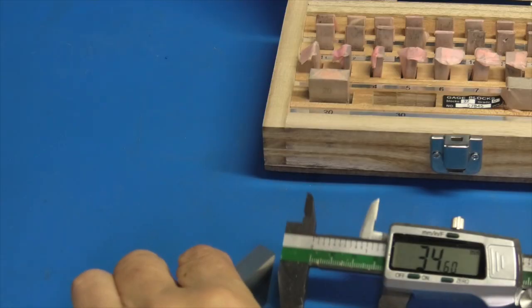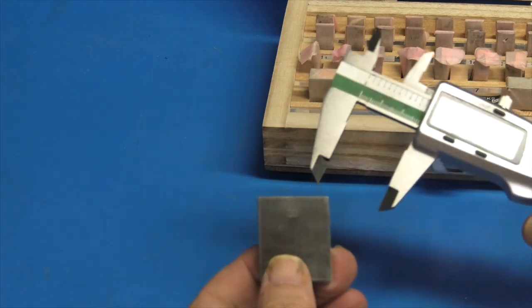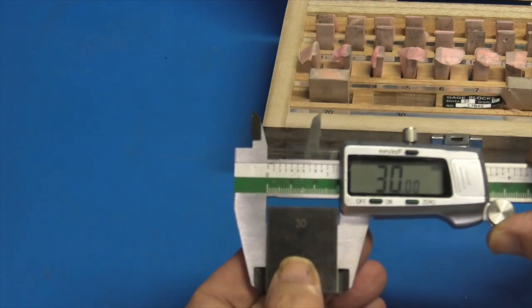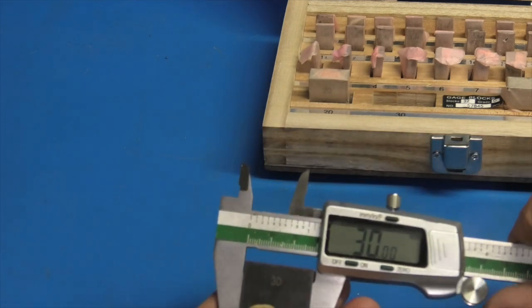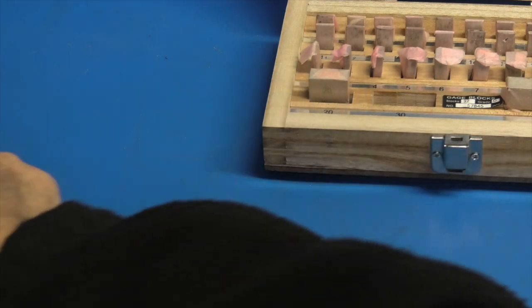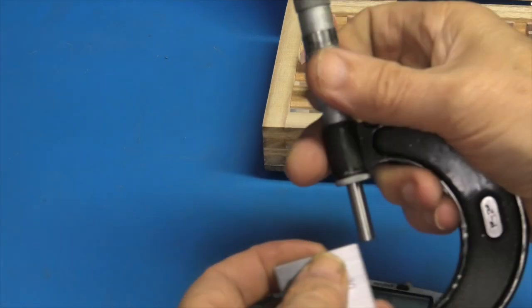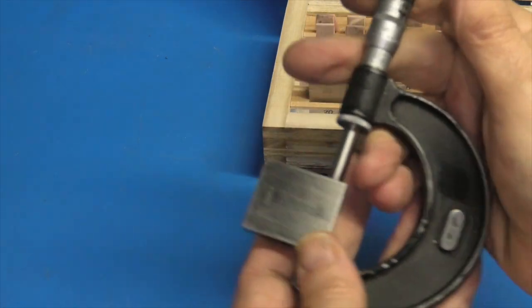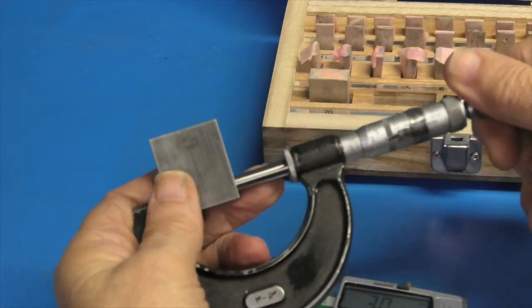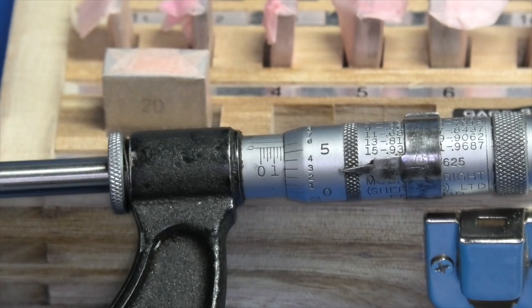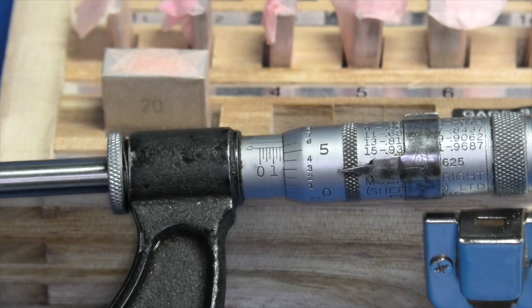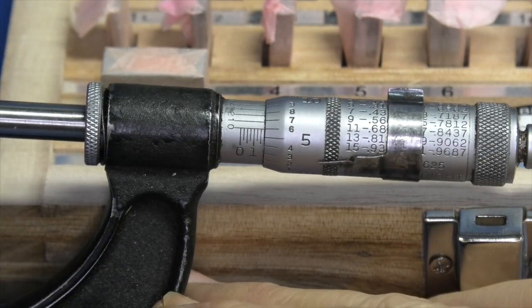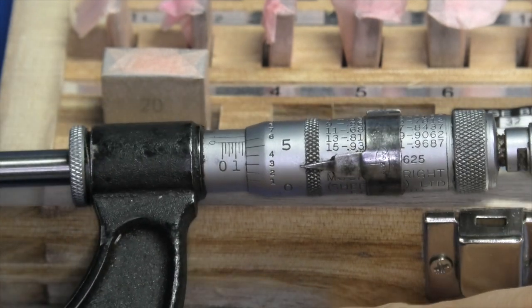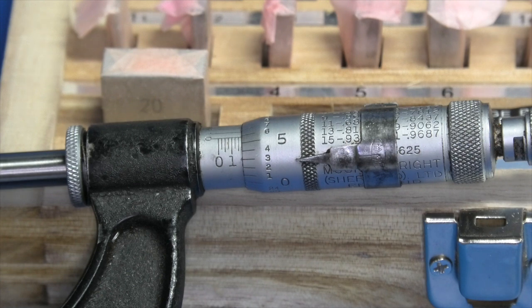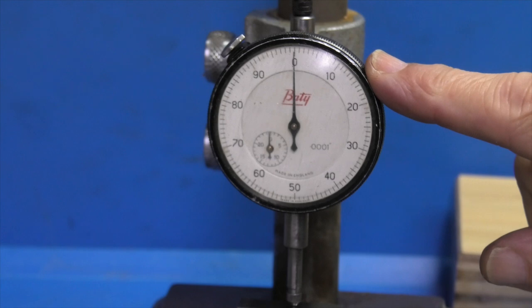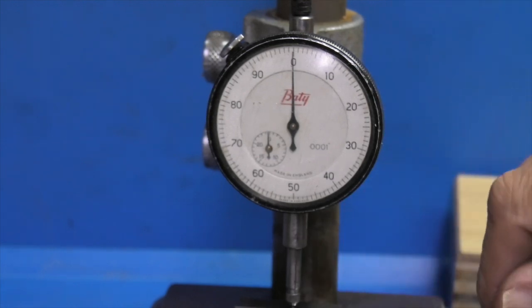I can use the 30mm slip gauge to check my digital caliper. See there, that's okay. And also check, this is a 1 to 2 inch mic. Just convert 30mm to inches. And that looks like 1.181 just over. And 30mm is 1.1811. Plus you can set your comparator with the slip gauge, whatever size you're looking for.